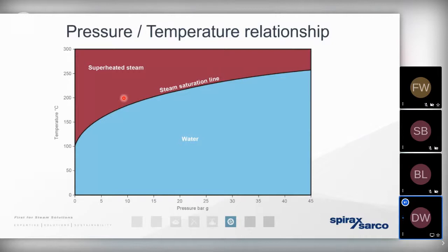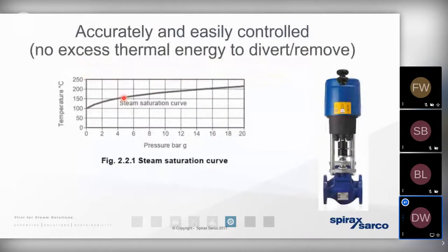But if we only want to use steam at a heat exchanger that requires a temperature of, say, 130, 132 degrees, it tells us that we can achieve that simply by reducing the pressure. So for that reason, we only actually need a two-port valve to control the release of energy from the steam onto the process, onto the heat exchanger.